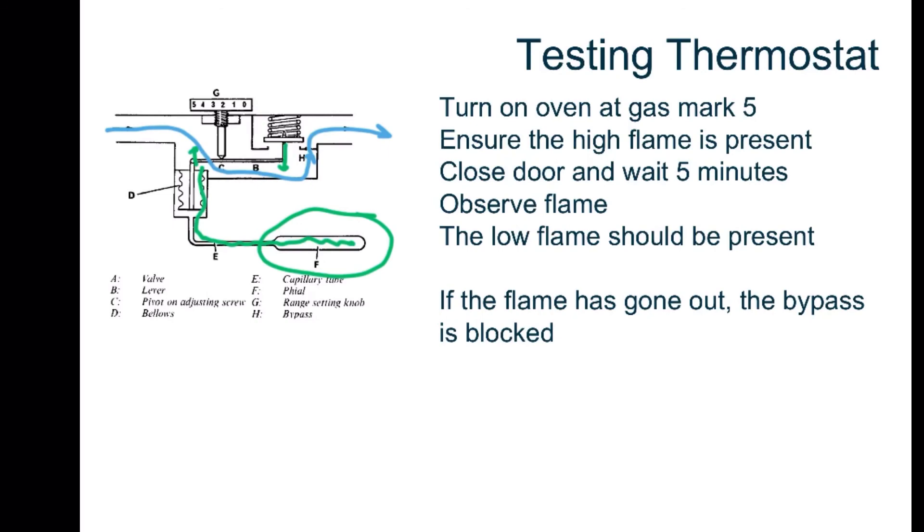So when you open the door or look in the glass window after 5 minutes, you should see a low flame. If you see a low flame, then the thermostat is working correctly. If the flame has gone out completely, then the only possible problem will be that the bypass is blocked.